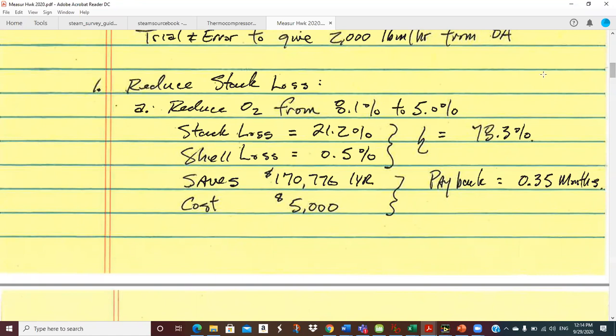Then I went back a second time to calculate my stack loss with the same temperatures and 5% O2 oxygen, which is reducing the amount of excess air — air that comes in cold and goes up hot. So I got 21.2% stack loss, and then half percent for shell loss. So from 76.1%, the efficiency improves to 78.3%.